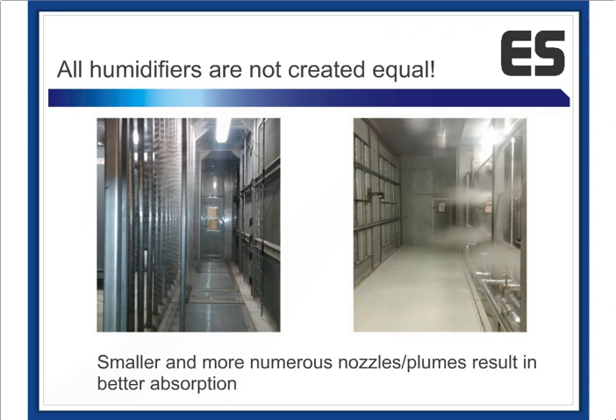So we have to be careful about how we introduce steam into our systems. The one on the right is a much later version in one of our newer research facilities—you can see there are more steam plumes, but they're very short and integrate more fully into the air handler. This speaks to the evolution of air handling systems: not only are they more efficient, but they can be smaller in size and less costly.